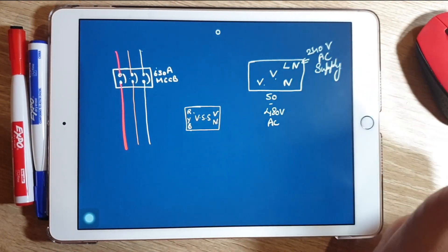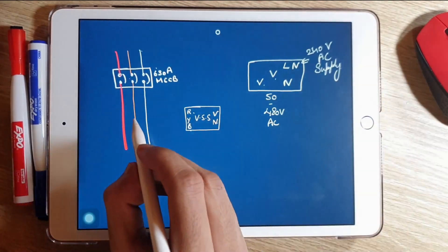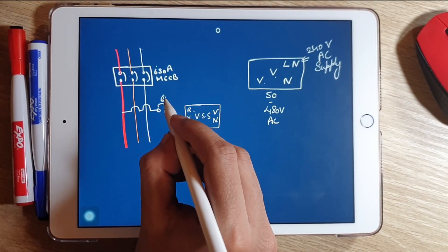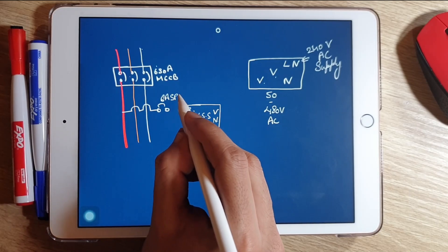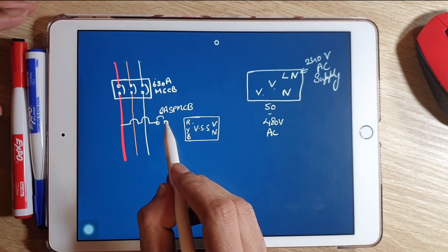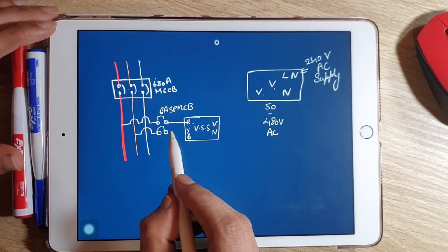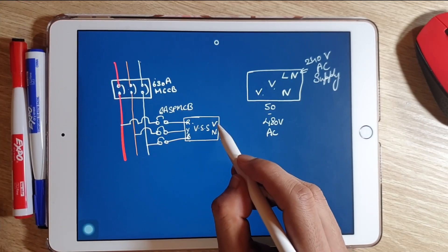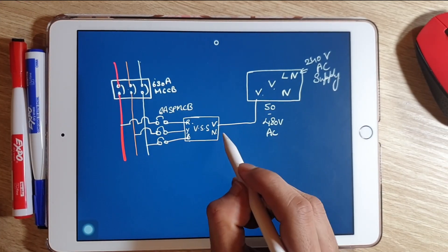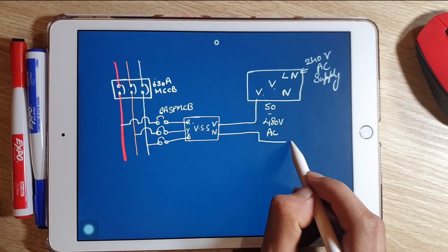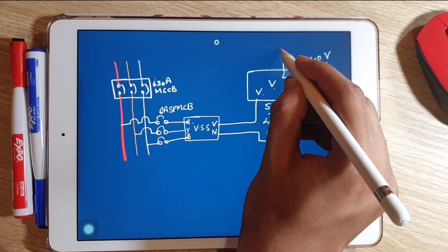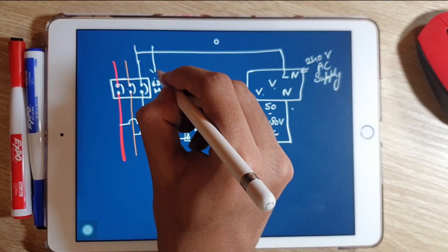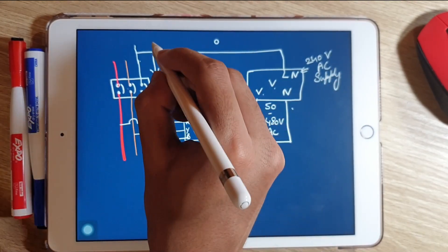The R phase is connected through a 6-ampere single-pole MCB to the R terminal of the voltmeter selector switch. Similarly, Y phase and B phase are connected to their respective terminals. The V-N terminals of the voltmeter selector switch are connected to the V-N terminals of the voltmeter, and a single phase and neutral is connected for auxiliary supply.